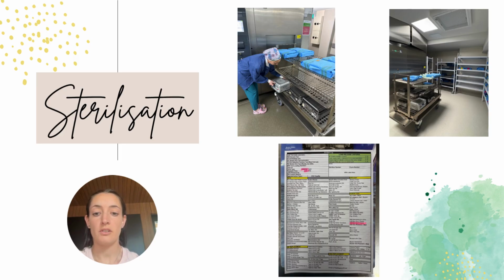I load the trolley inside the sterilizer and I start the cycle, which lasts just over an hour. When the cycle is finished, I use a long hook stick to take out the cart from the sterilizer. On the other side, as we have a pass-through sterilizer, I check that my container is all intact, and properly sterile by checking all the indicators. I check also that the sterilization indicator label didn't fly off in the sterilizer and is still on the container.